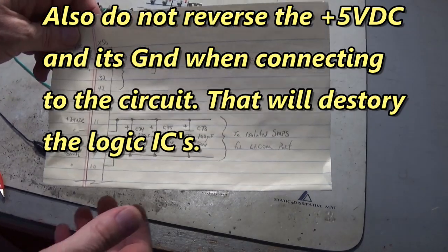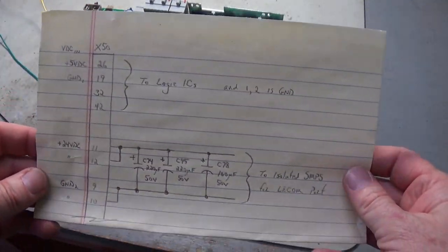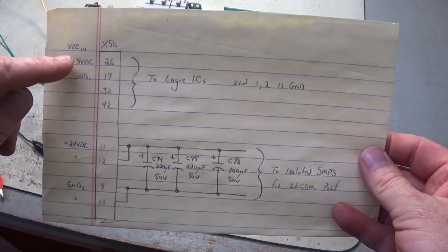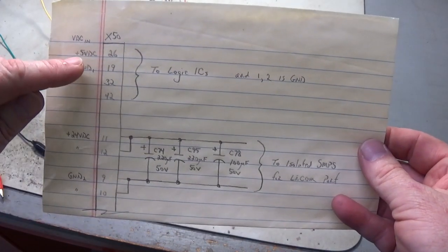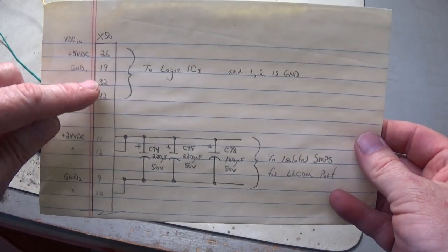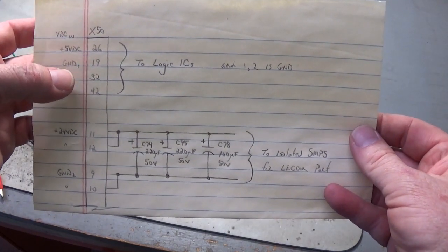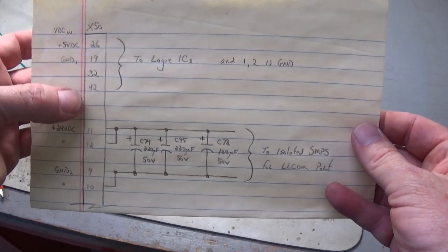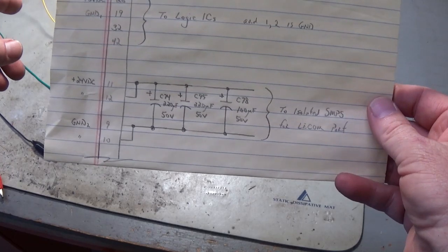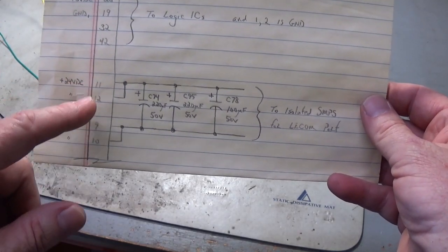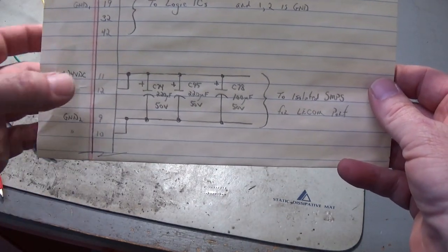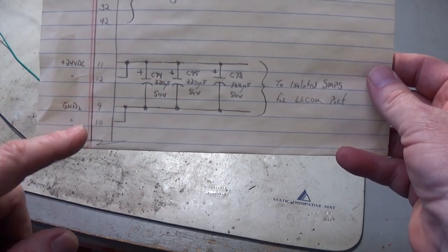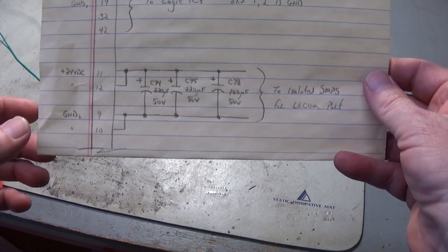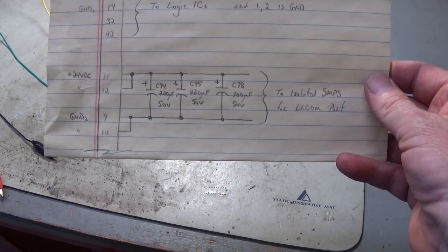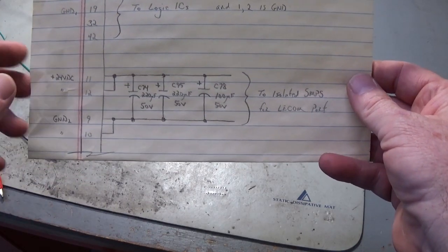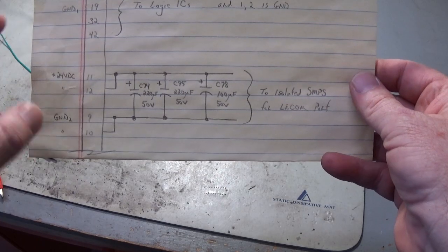Here's my diagram that I use. I'll put this up at the end of the video, but the 5 volts goes on the X50 stake connector on pin 26, and there's 3 logic grounds, one on 19, 32, and 42. Those are your 3 ground pins. To power up the Lenze COM port over there, you need to put 24 volts on pin 11 or 12, they're tied together, and it's ground on 9 and 10. Either one, they're tied together. That's an isolated COM port over there, that's why you need to put this 24 volts, and it's ground on those pins right there.